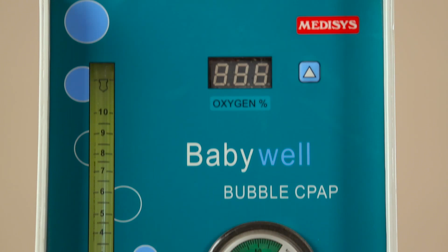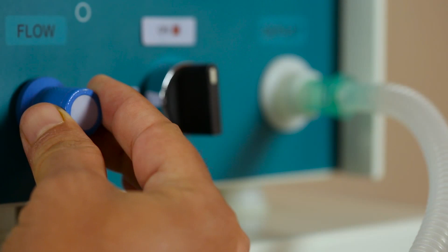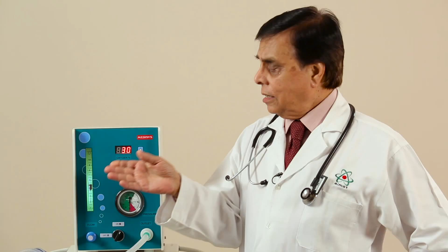So what are the special things about this machine? First thing, we got rid of the most bulky part of the machine, that is the compressor. The air compressor, which is a very important part of it, we got rid of it, and instead, for the first time, we have incorporated a turbine driven machine. So that has enabled us to give you a very small machine which is very easy to control. Second feature is that the oxygen blenders in other machines are bulky, and then you have to do manual rotation, manual adjustments, in a very different way. So we got rid of that and we put in an electronic oxygen blender, which is very simple to adjust, and you can just increase or decrease the oxygen and then you get the percentage over here. This is the beauty of the electronic oxygen blender.